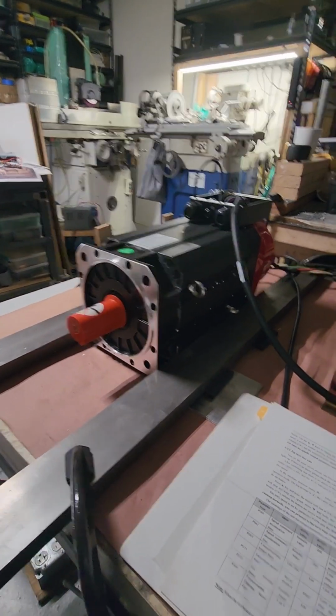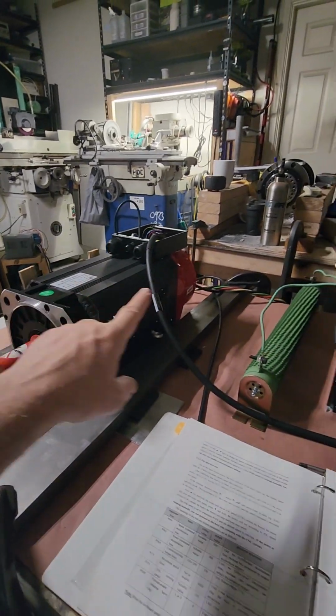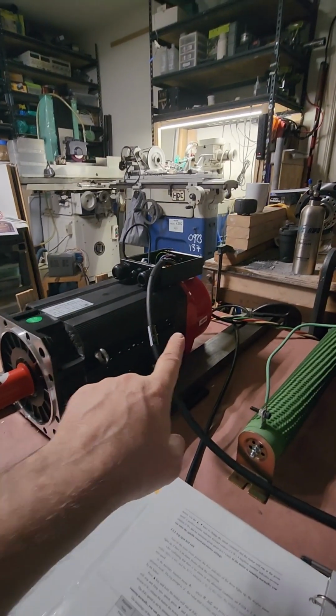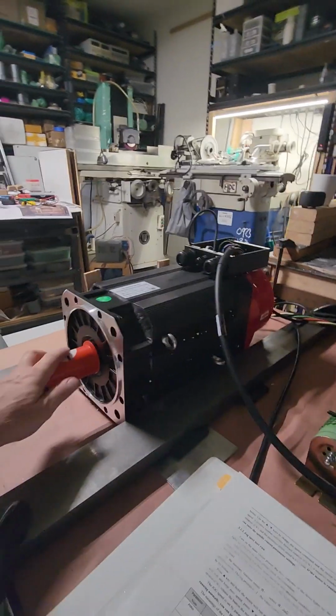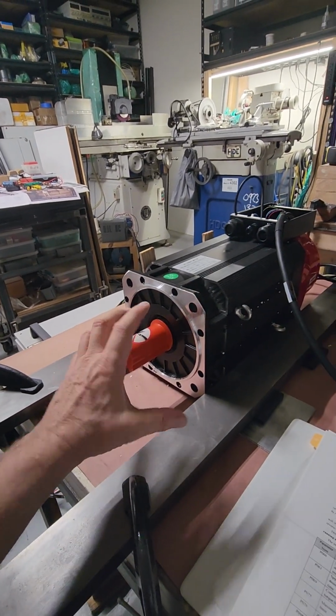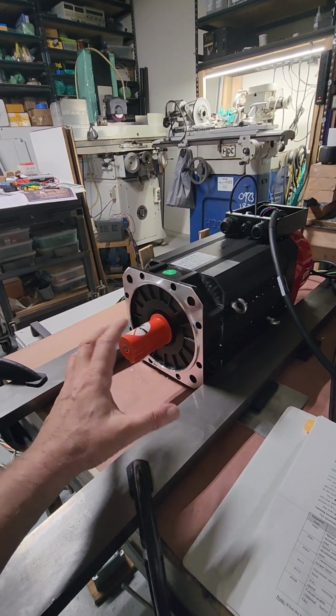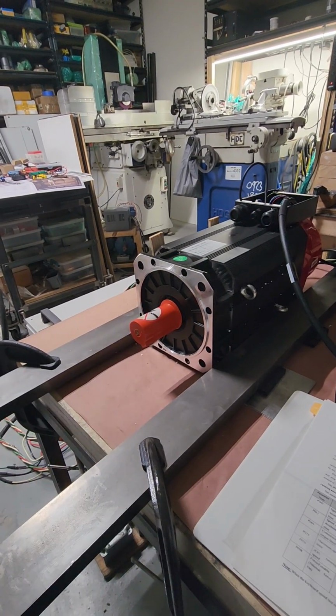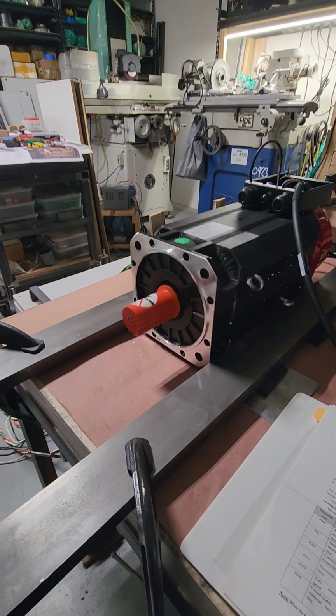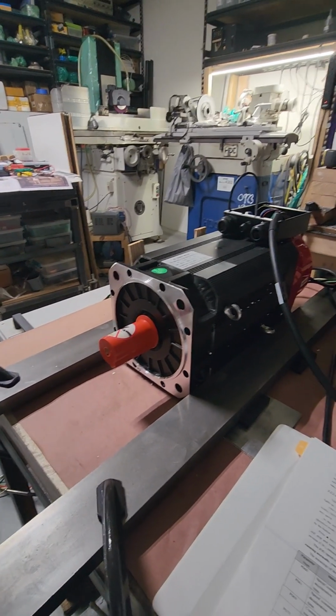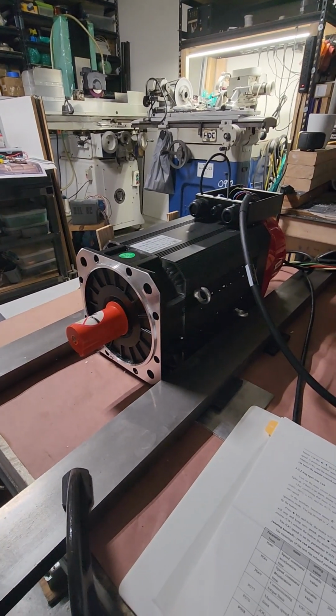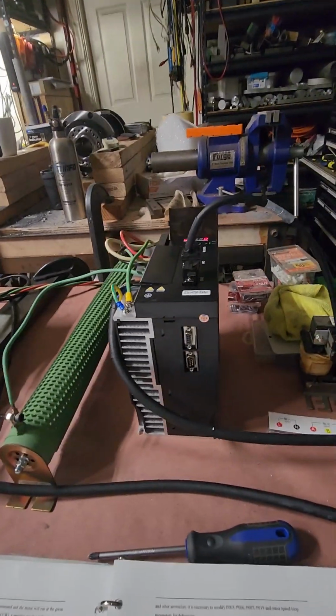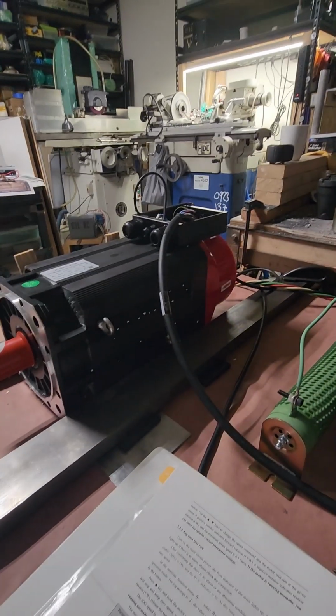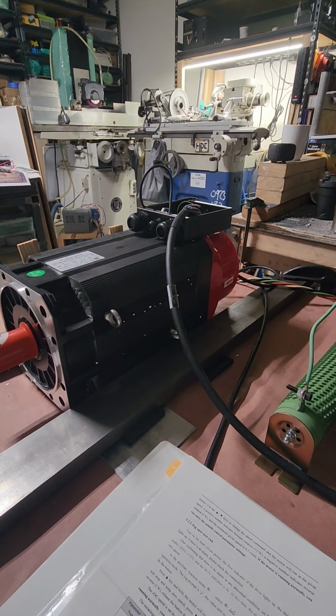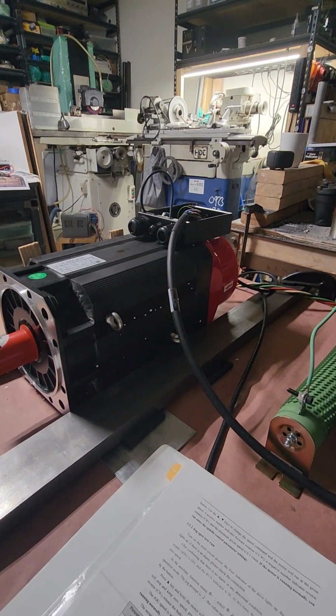Now, for position, what I don't like is the encoder is only 10,000 quadrature pulses per revolution, so that's not a lot. If you want any precision positioning, you need a better encoder. This is an incremental encoder, not one of those digital encoders with a serial protocol — you just have the A, B, and Z differential lines coming into the controller. What I'm planning to do to get better resolution is change that encoder for one which gives me 255,000 points per revolution.